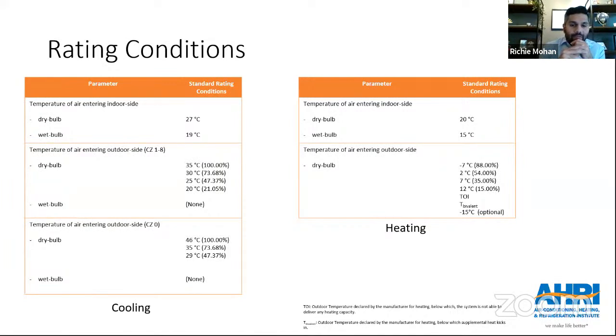Currently, if we were to reduce 27 to another temperature, any current test data or measurement data we were planning to use or leverage for this global standard could no longer be used, which increases the burden, or the work, on manufacturers to develop the ratings by tenfold. So the intention is to keep it at 27 degrees Celsius, at least for the first iteration or first version of this test procedure, so we can provide additional time to manufacturers and the rest of the VRF community to work on ratings and testing at a lower indoor dry bulb.